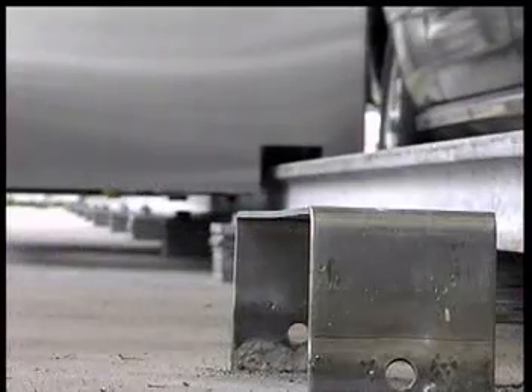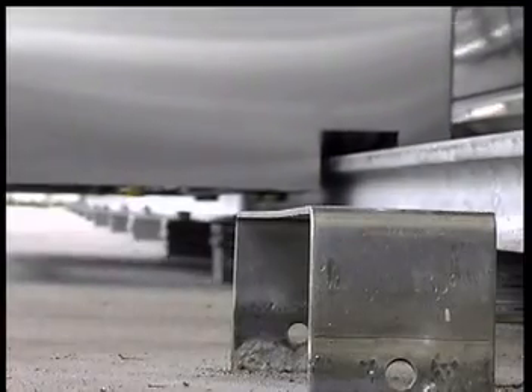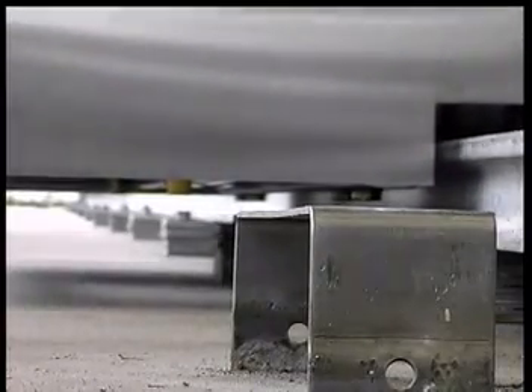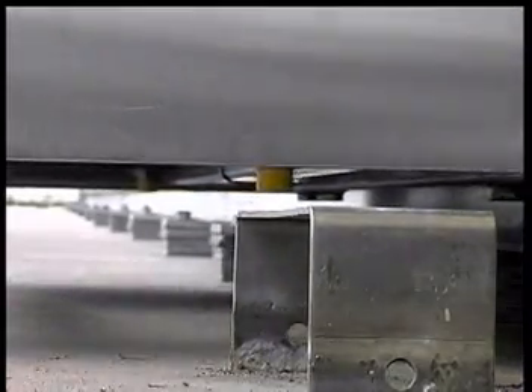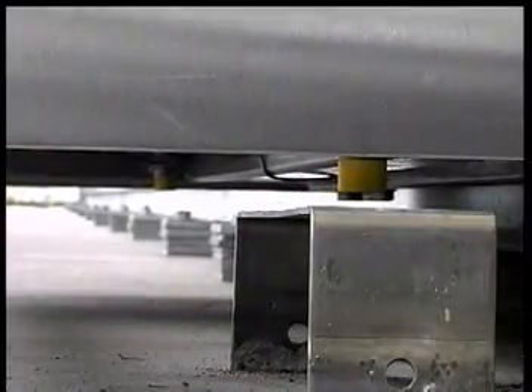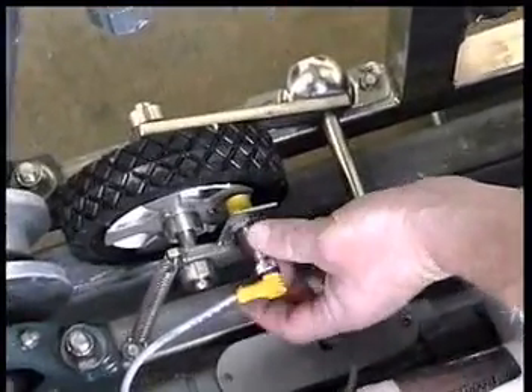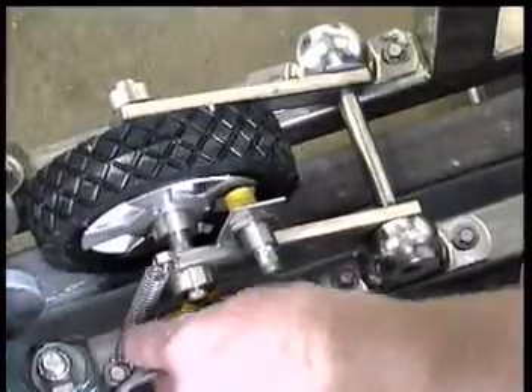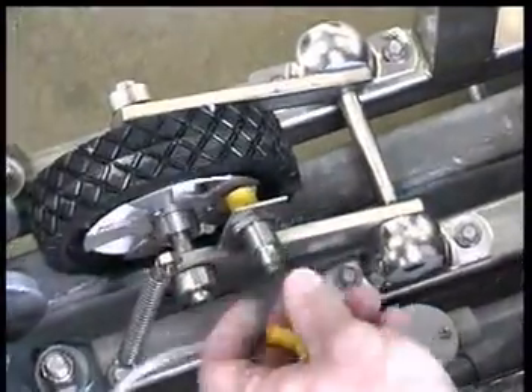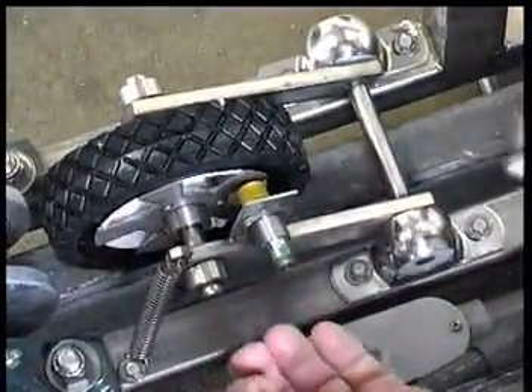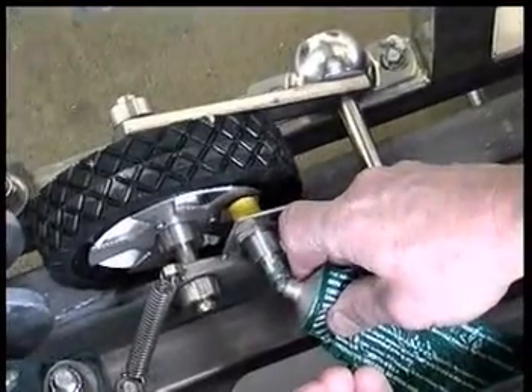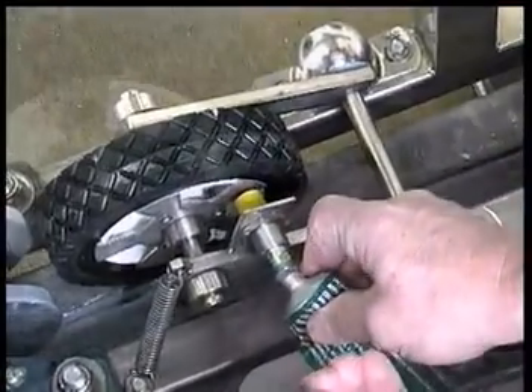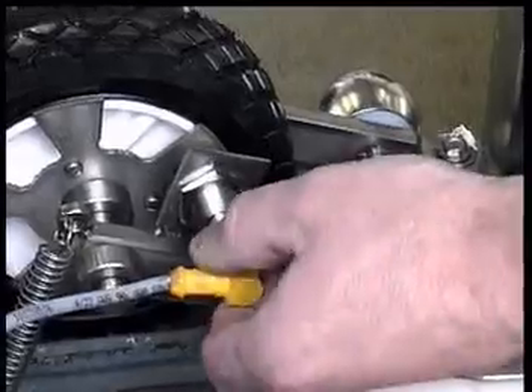The end of track and home positions proxes are to be mounted on a parallel plane with the prox's travel path to ensure a constant signal over the entire target. Signal wires are connected to the prox using an O-ring fitted screw-on connector. Moisture on the terminal pins can cause false signals. Filling the connection with electrical grease before attaching the screw-on connector will protect the connections.